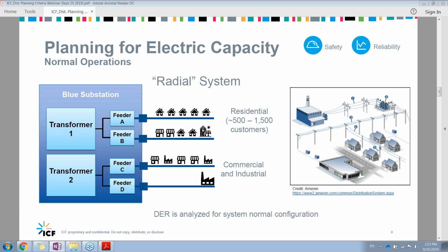Real substations that serve moderately populated areas typically have multiple feeders and perhaps multiple transformers. So on the left-hand side of the screen, what we're showing is this hypothetical blue substation that has two transformers and four feeders that serve a mix of residential, commercial, and industrial customers. So a feeder serving purely residential customers may have around 500 to 1,500 customers. A feeder that's serving a large industrial plant may be dedicated to that plant. And this is sometimes called a radial system because the feeder emanates from a source and goes in one direction, or radiates out into the field, and it's not networked together, which would be the other type of system.